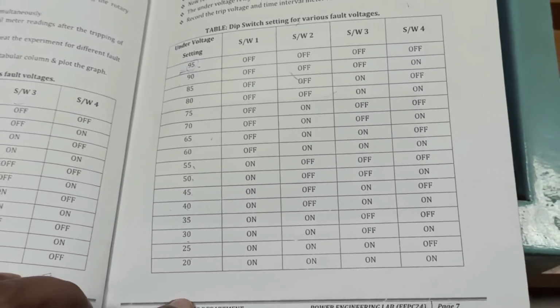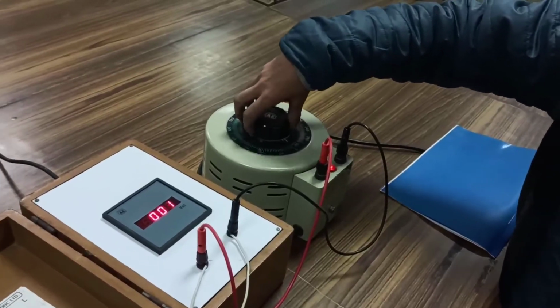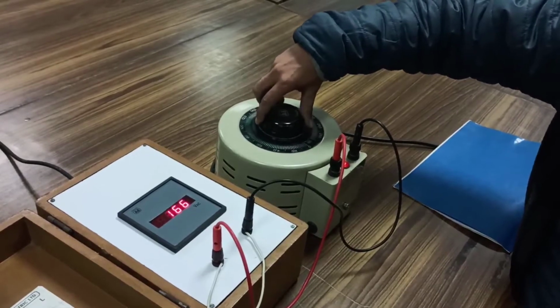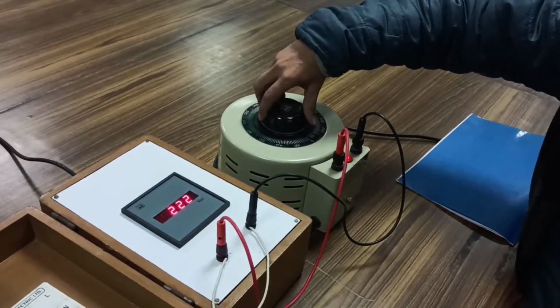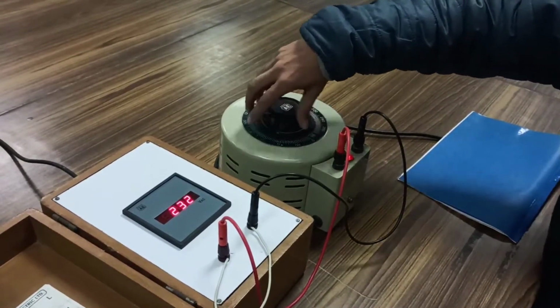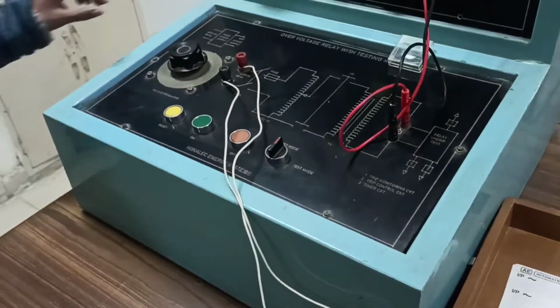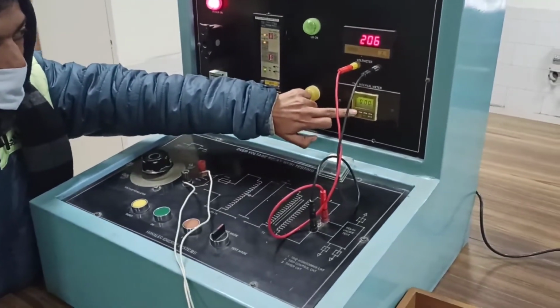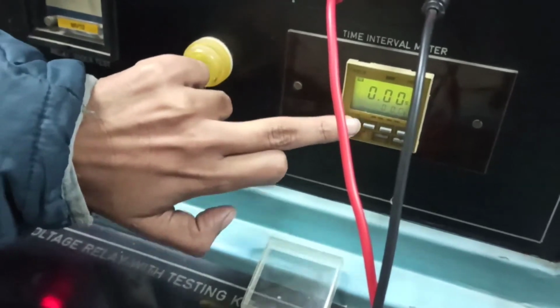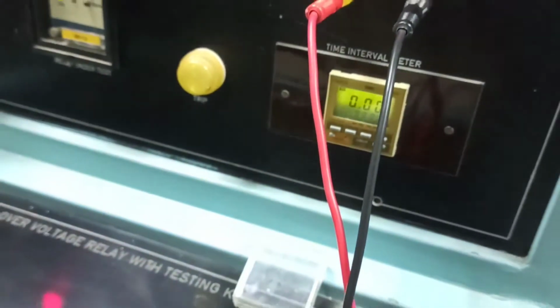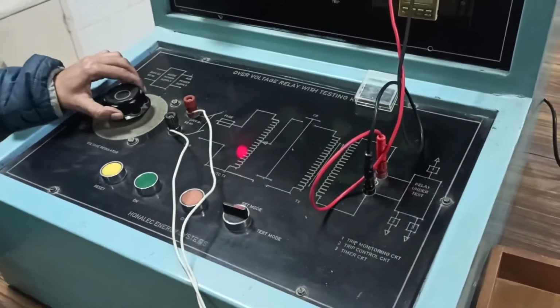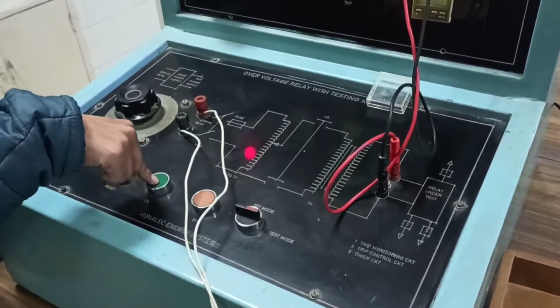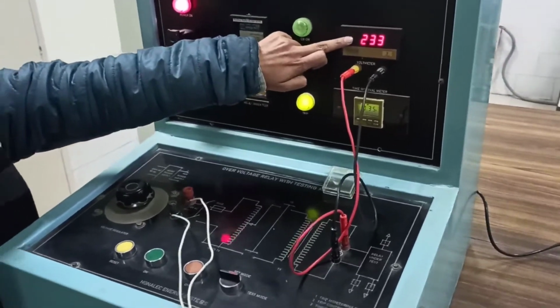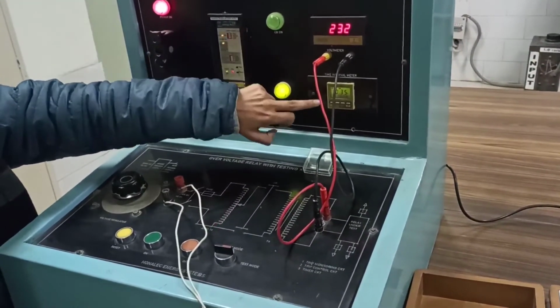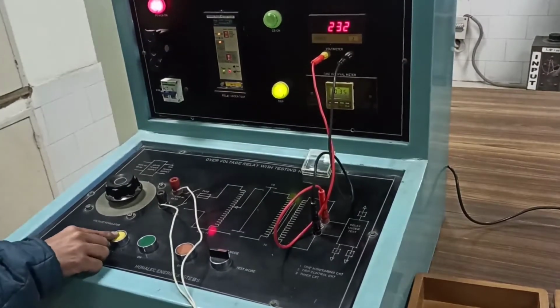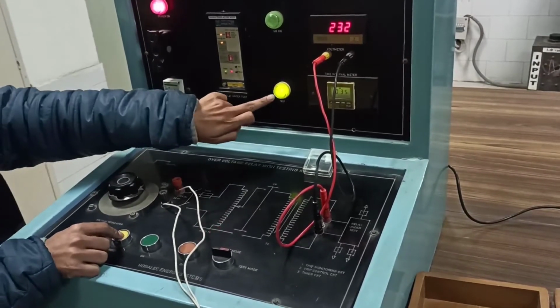Now we will perform the experiment. Now slowly increase the voltage to 230 volt. Set the supply voltage to 230 volt. Now switch on the kit. Set the time at 90 seconds. Press the first switch. Now set this switch into test mode and set the maximum voltage. Switch on. At 232 volt, which is the supply voltage, the fault voltage, the trip time is 0.35 seconds. Now reset it. Press the reset switch until the trip light is off.